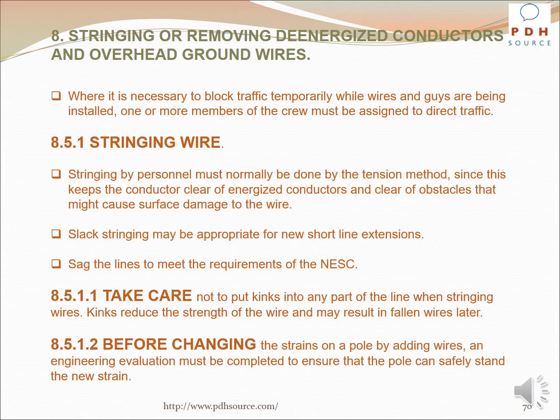Slack stringing may be appropriate for new short line extensions. Sag the lines to meet the requirements of the NESC. Take care not to put kinks into any part of the line when stringing wires. Kinks reduce the strength of the wire and may result in fallen wires later. Before changing the strains on a pole by adding wires, an engineering evaluation must be completed to ensure that the pole can safely stand the new strain.